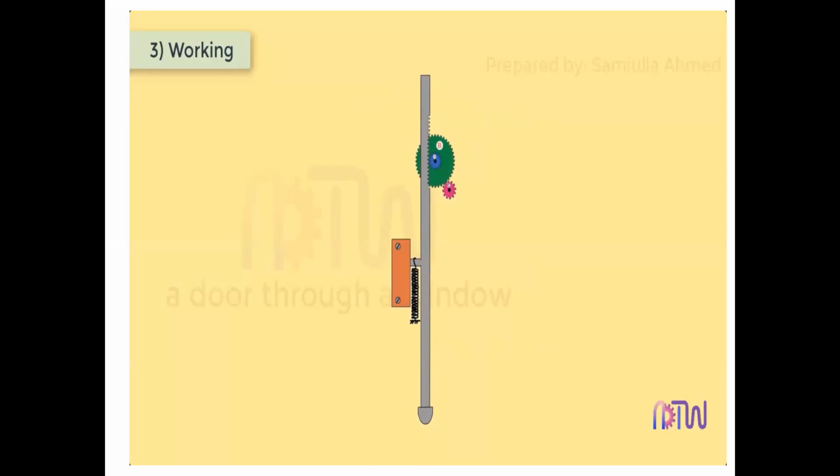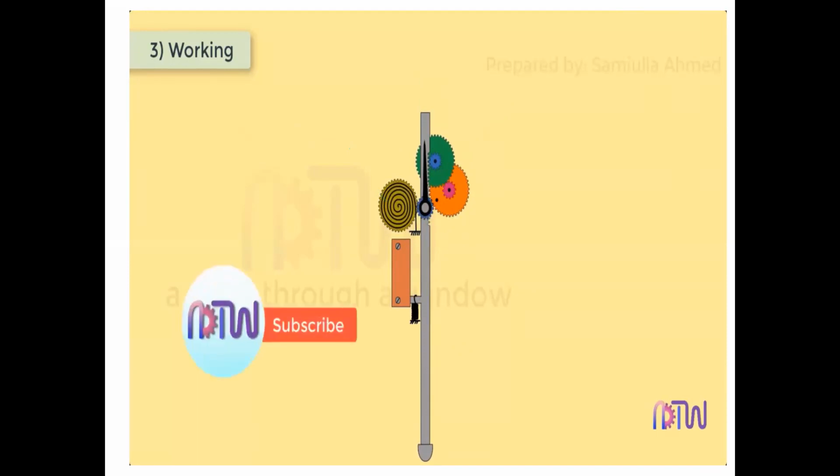Attached to the second pinion C is another gear. This magnification is further enlarged at the tip of the pointer by an amount depending upon its length. In order to take up backlash, a light hairspring H is always fitted to the dial gauge gear trains by meshing a gear F to pinion E and attaching the spring with gear F, also to prevent gear backlash. The gears are precision cut, and the movement assembly resembles that of a high-grade watch.